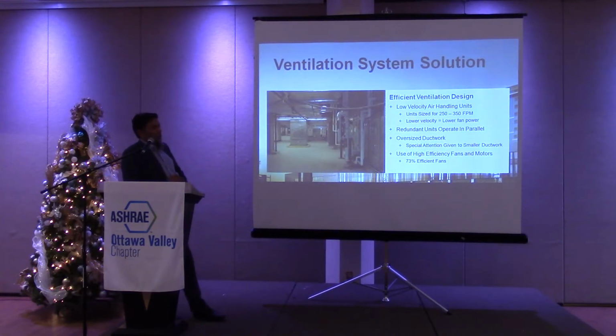Now, the reason why it makes sense in healthcare is because of the CSA standard requiring minimum air changes per hour for spaces. So you're operating those units at 100% of the time. In a VAV system, you don't get that same sort of benefit. So it does make sense. These spaces, maybe in lab spaces, depending on the approach.